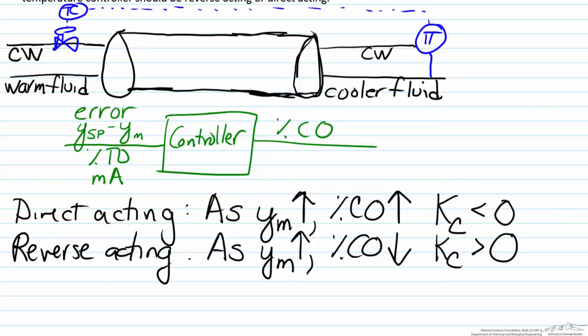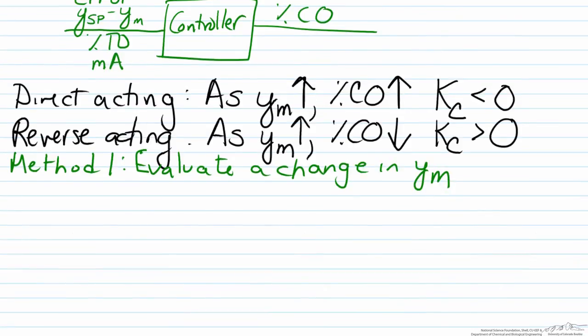The first method is to evaluate a change in the measured variable. For the heat exchanger, the value we are measuring here is the temperature of the process fluid. If the fluid temperature goes up, in other words the process fluid temperature is too high, we are going to increase the cooling water flow rate.